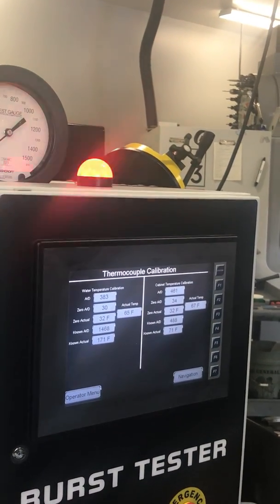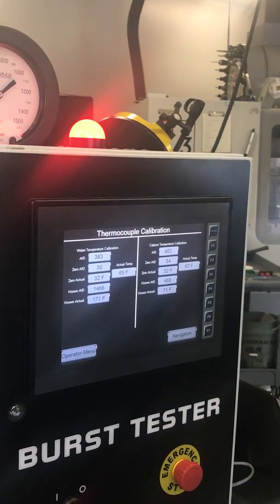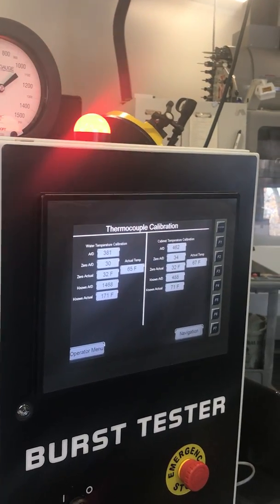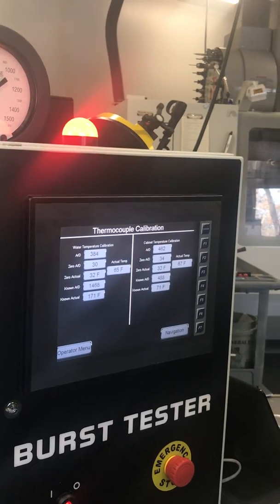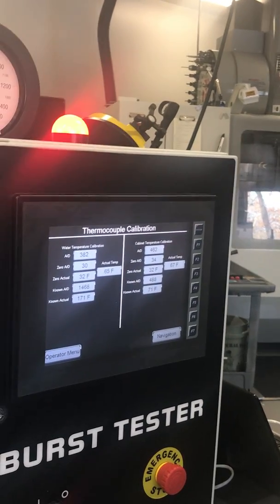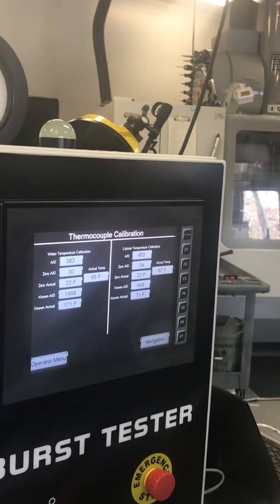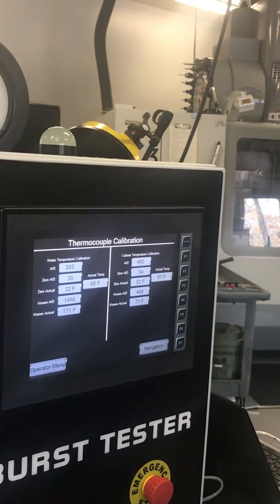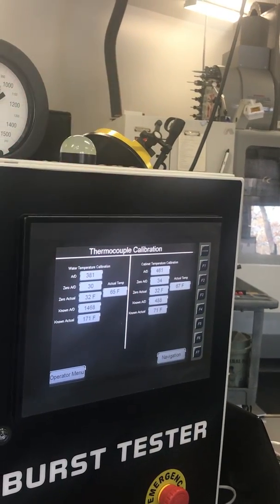I think it's a plus 30. I don't think so, because it's voltage. I'm looking at this number and I don't know what it is. So we did the same thing here. This isn't as easy to calibrate. We had to pull them out and stick them in ice water and then hot 170 degrees Fahrenheit water. It was 171. We zeroed and spanned them at those two points, and you shouldn't have to touch them.